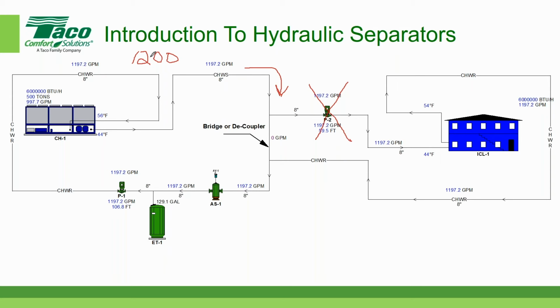That means that the entire 1,200 gallons per minute is going to run across this bridge here. And so the flow across the bridge is not going to be zero. It's going to be equal to what we just said, 1,200 gallons per minute. The flow in the secondary loop, because our secondary pump is off, is zero. So we'll put a zero over there. So all of the flow is running across here. Now, one of the characteristics of a bridge or a decoupler, sometimes again referred to as a zero pressure bypass.